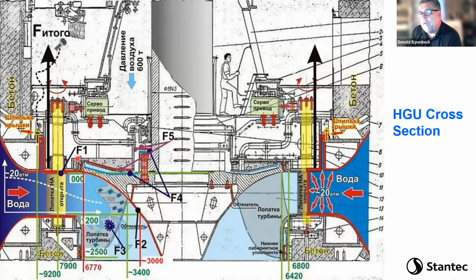So this head cover, from about this point where my cursor is, where it says F1 over to the left edge, that is subject to the high pressure from the upper reservoir at 230 meters of water pressure from here to here. From inside this seal here, the area underneath here is actually connected to the draft tube in the lower reservoir level. So this is a low pressure. And so what they use is the weight of the rotor and the generators to counteract this uplift thrust on it. And so you see the cone here, the thrust cone, and there's another 600 tons of down pull that occurs when we're producing the turbine. So it wants to go down, it doesn't want to go up. There's enough dead weight plus the down thrust to counteract most of the uplift that would occur on the head cover.